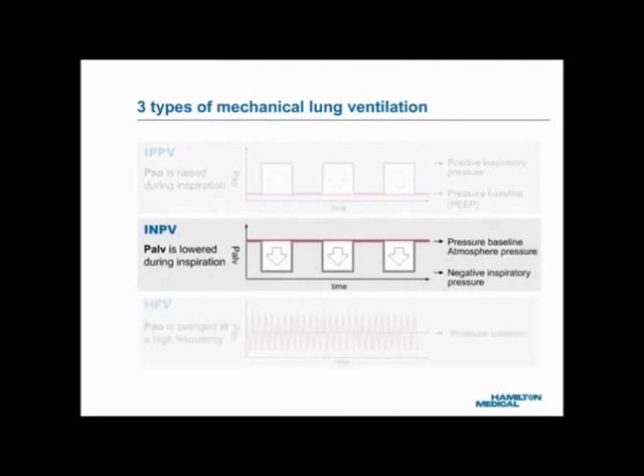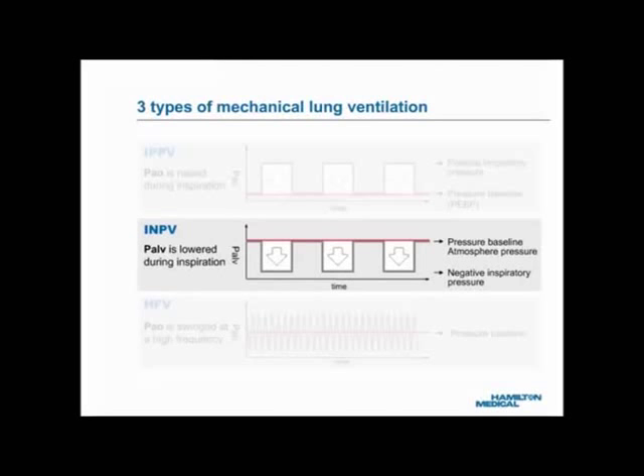Two: the center graph shows the pressure waveform for INPV, or intermittent negative pressure ventilation. Using this principle, a negative alveolar pressure, or PALV, is applied below the pressure baseline. The negative PALV sucks air into the lungs. The baseline is usually local atmospheric pressure.